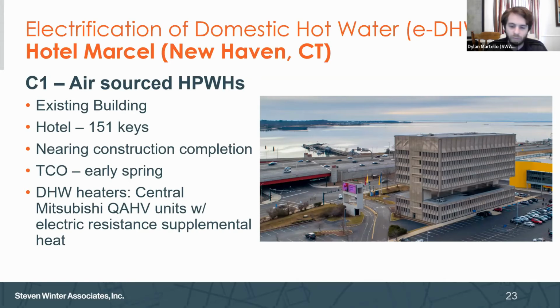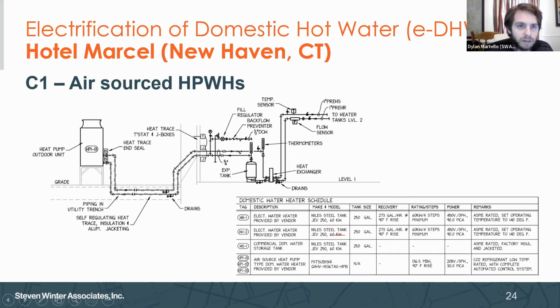It is undergoing the commissioning phase right now, so we're right in the middle, in the heart of it in terms of getting the system up and running. They're using the centralized approach, air source heat pump water heaters, specifically the Mitsubishi QAHV units. They do have electric resistance as supplemental heating for backup, in case the heat pumps need the extra capacity. So we have a diagram here showing the outdoor QAHV Mitsubishi units, and there is some heat tracing on the piping on the outside, just to deal with the outdoor pipes.